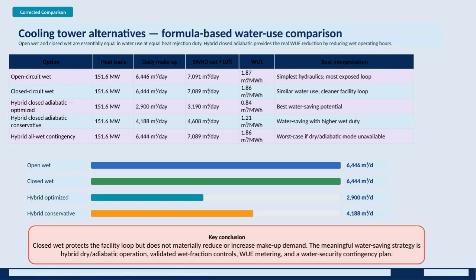Here we compare different cooling tower alternatives based on their water use efficiency at a consistent heat rejection duty of 151.6 megawatts. You'll see that open circuit wet and closed circuit wet systems have almost identical daily water makeup demands, around 6,444 to 6,446 cubic meters, resulting in virtually the same water use efficiency, or WUE, of approximately 1.86 to 1.87 cubic meters per megawatt hour. Closed wet systems do offer the advantage of a cleaner facility loop, which helps protect equipment, but they don't significantly reduce water consumption compared to open wet systems.